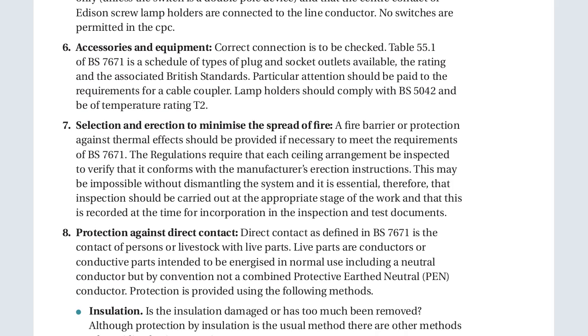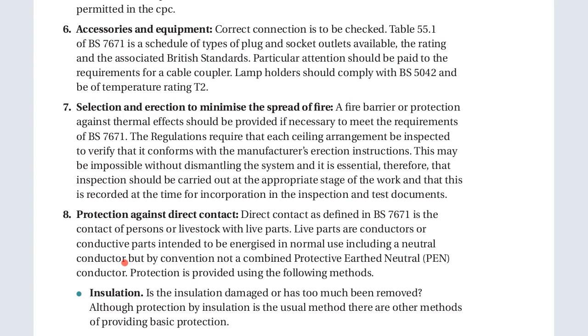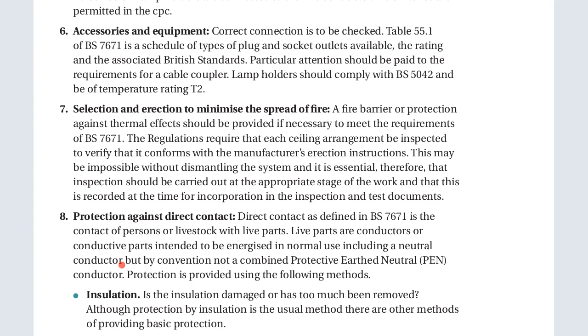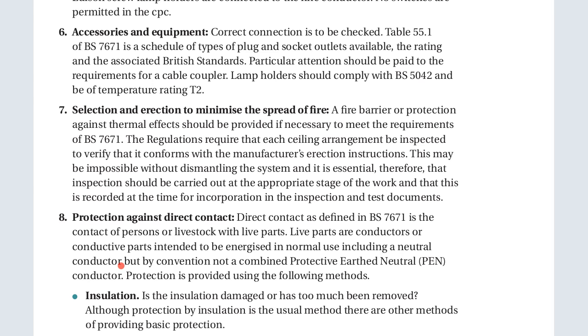Another one is the selection and erection of equipment to minimize the spread of fire. So a fire barrier has to be provided. That is, the fire barrier or protection against thermal effects should be provided if necessary to meet the requirements of the BS standard, that is 7671. The regulation requires that each fire barrier arrangement be inspected to verify that it conforms with the manufacturer's erection instructions. This may not be possible without dismantling the system, and it is essential, therefore, that inspection should be carried out at the appropriate stage of the work, and that it is recorded in time to incorporate it in the inspection and test documents.